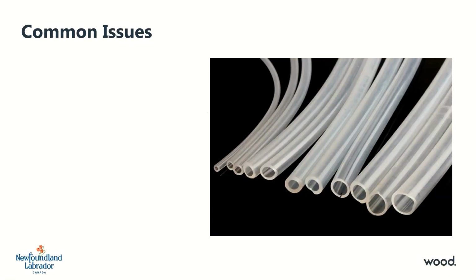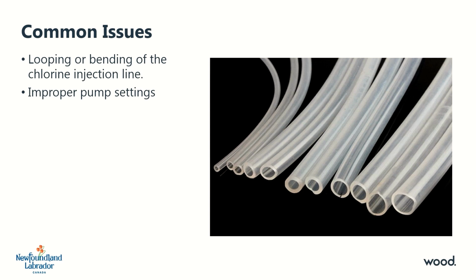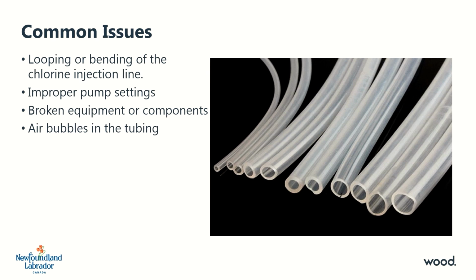Before we begin discussing common issues, operators should note that one of the best sources of troubleshooting and maintenance can be found in the pump manuals. There is usually a section at the back which lists common problems and possible solutions. Some common issues that are regularly encountered with a chemical feed pump include looping or bending of the chlorine injection line, improper pump or flow meter settings, broken equipment or components, air bubbles in the tubing, ruptured or damaged diaphragm, and clogged injector fittings. Now let's discuss these issues in more detail.